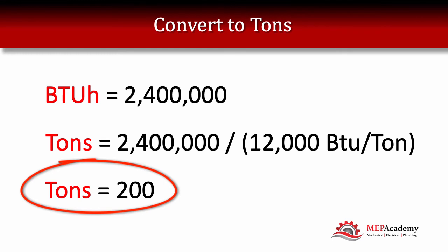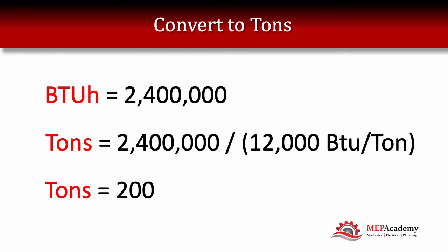It's a simple formula, and you can turn it around to determine GPM if you know the BTUs. This is a quick way to determine the tonnage of whatever waterside piece of equipment you're measuring, if you have the GPM and the Delta T.